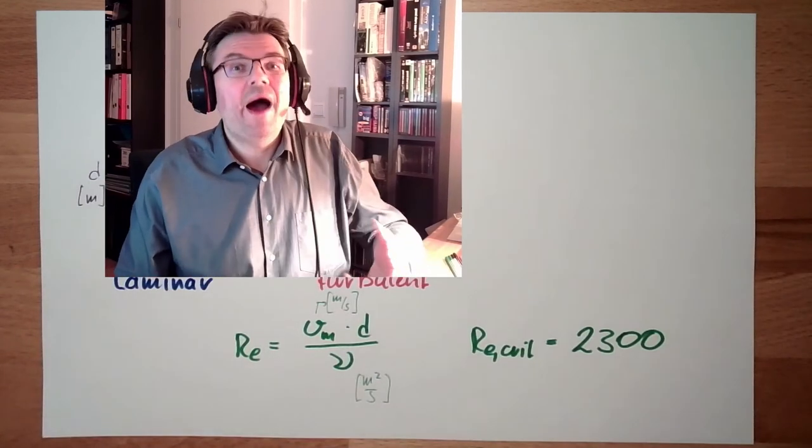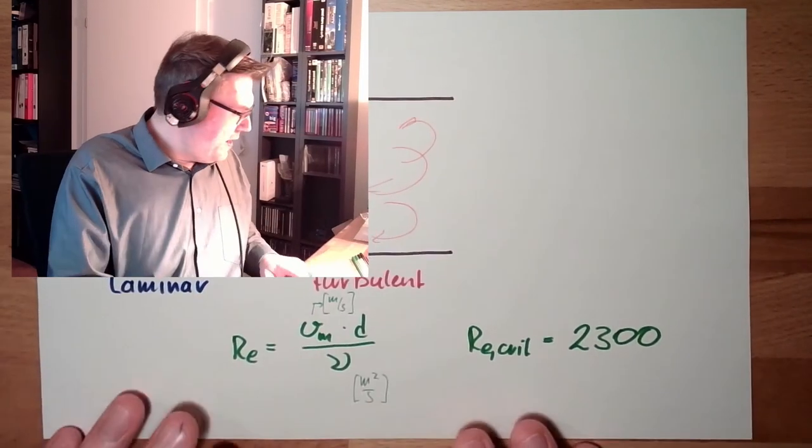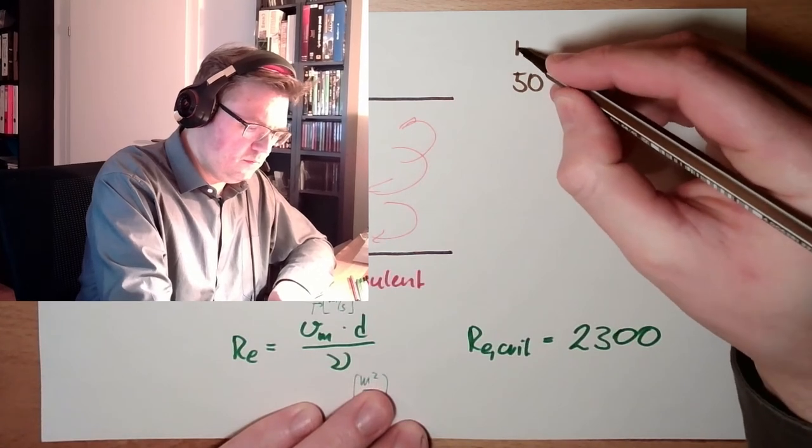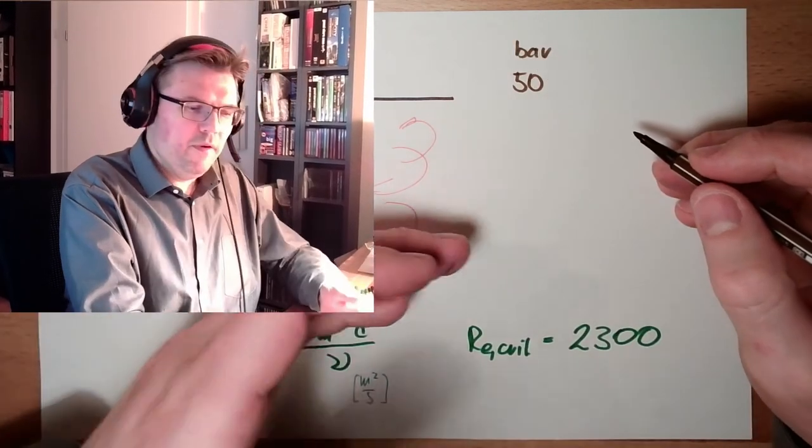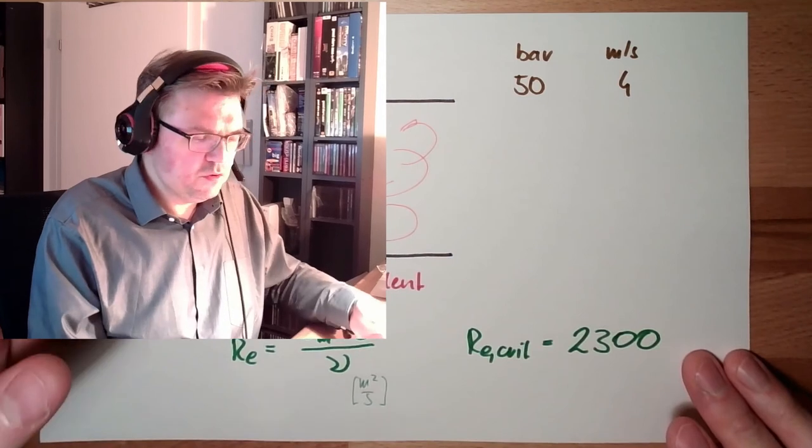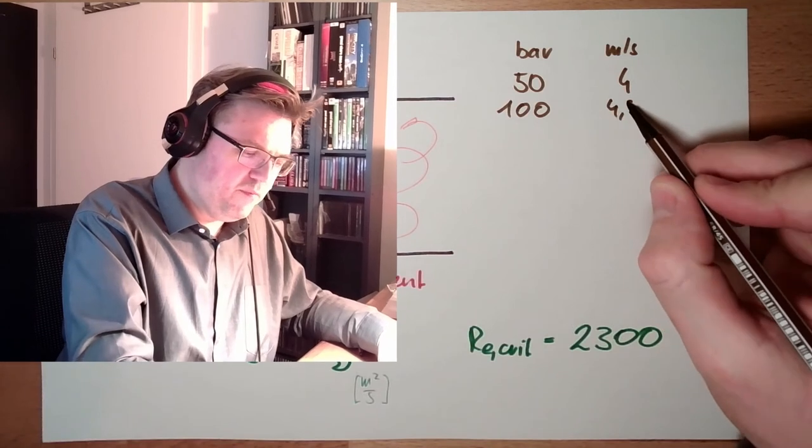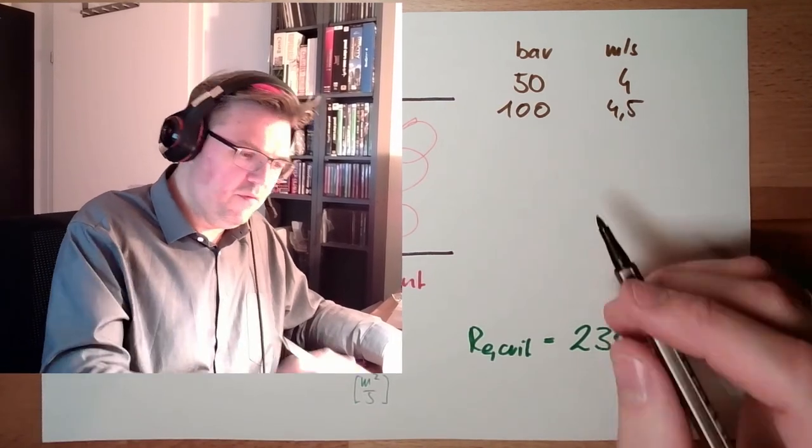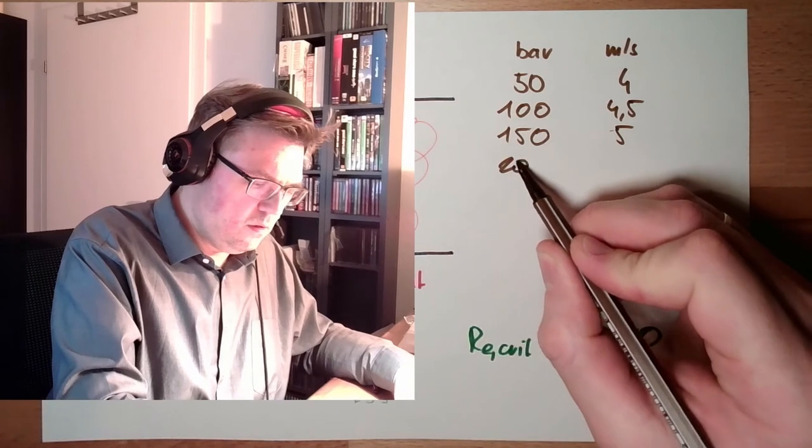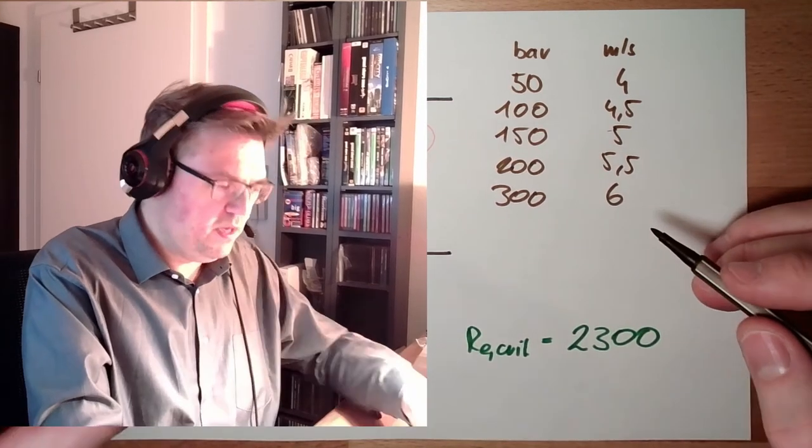With higher pressure, we can go at higher speeds. This means, if our pressure line here has around 50 bars, we can go with speeds around 4 meters per second. If the system has not only 50 bar, but 100, then we can speed up to 4.5 meters per second. If we have 150, we can have around 5 meters. If we have 200, we can have 5.5. If we have even 300, we can go up to 6 meters per second. Speed of the liquid.